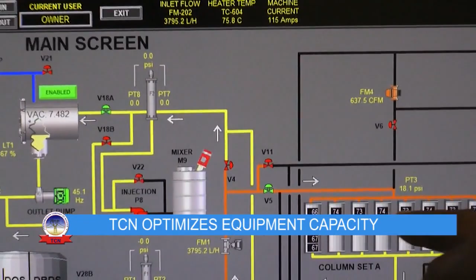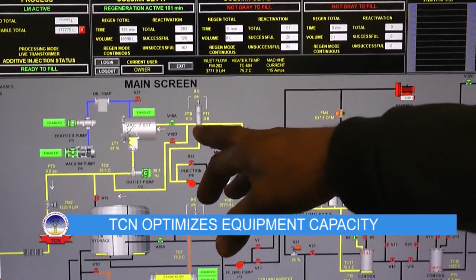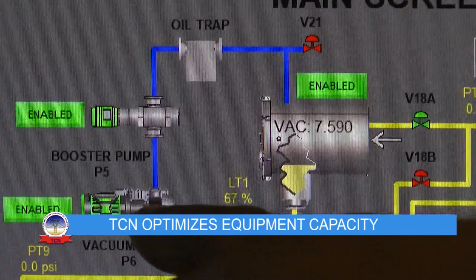This inlet pump sucks the oil from the transformer through the inlet pump. It will hit the heater that heats up the oil, then go to filter one, which will grab the internal particles that are inside, then pass it to the column. This is the column, this is where the major work is done. That removes the water, grabs the water and the sludge, then back to the pot. From the pot now, we send it to filter 2, which grabs the tiny particles, then passes to the vacuum bypass, vacuum chamber, and vacuum pump to the booster. Then we remove the escaping water going to the transformer.